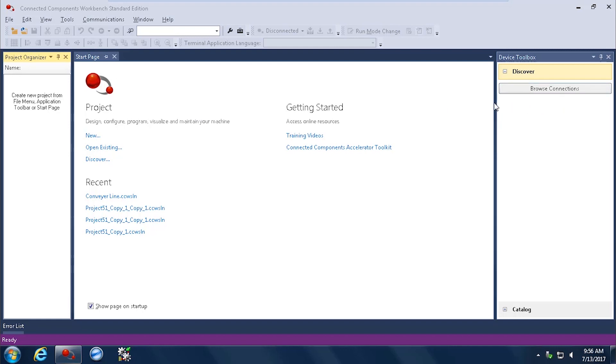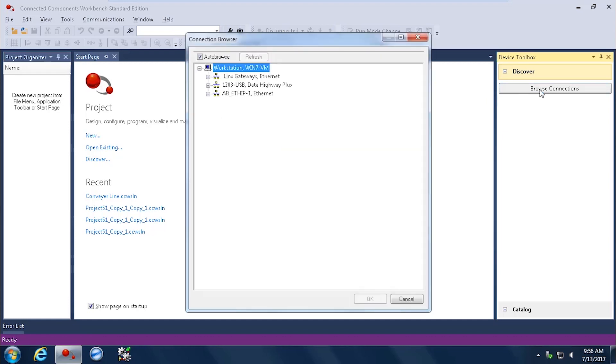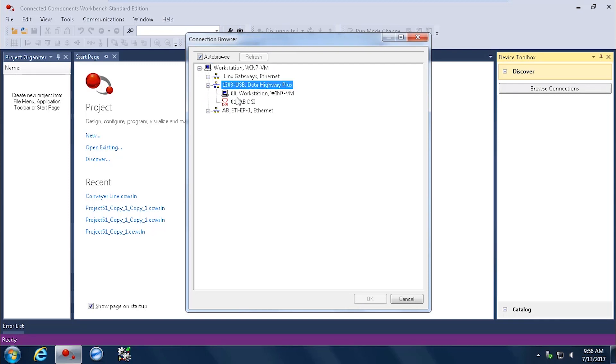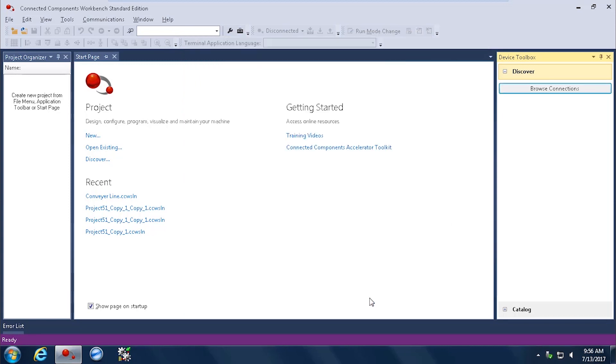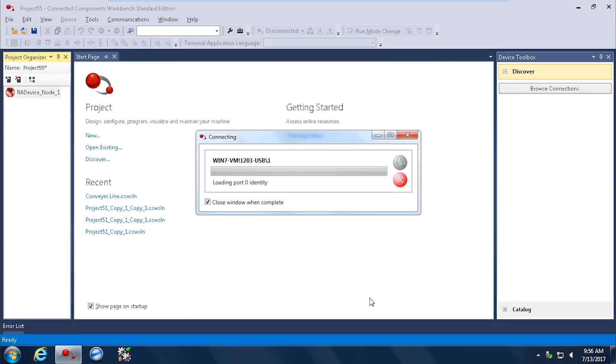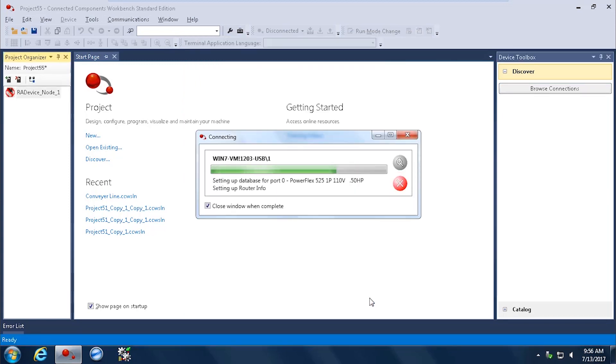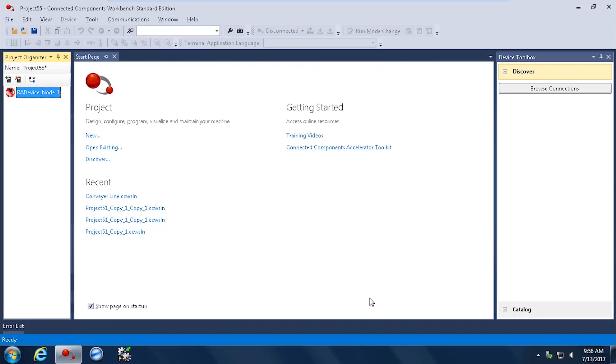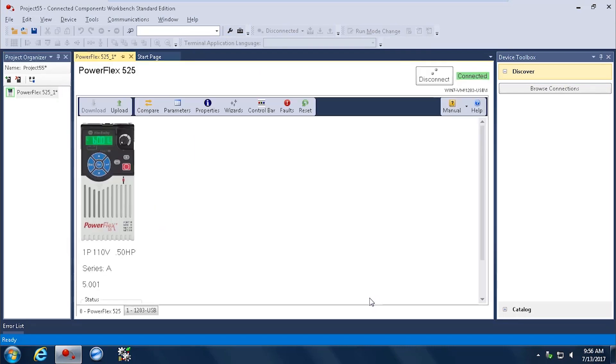Now we can click over on Browse Connections, because this is where we're going to set up the different drivers we have available as RSLinx is embedded inside Connected Components Workbench. And here you can see from the drill down of the 1203 USB, the DSI port of our PowerFlex 525 is available, and now it is uploading and connecting to that drive. You can see the drive is now available on your screen.